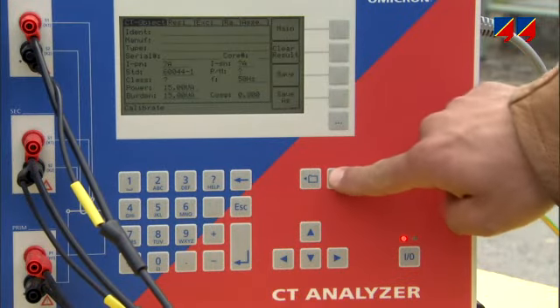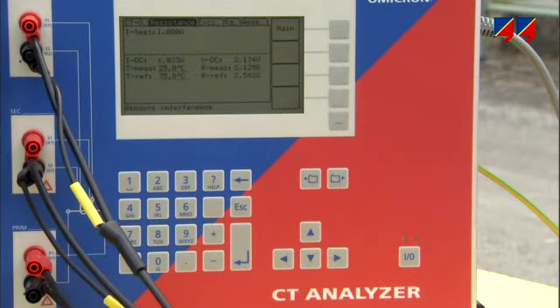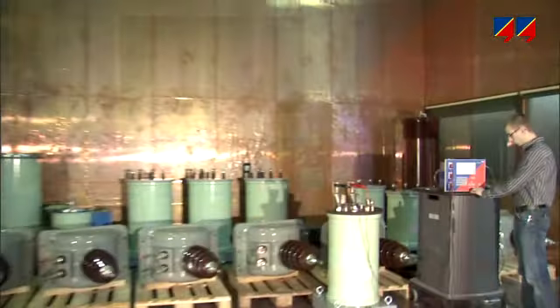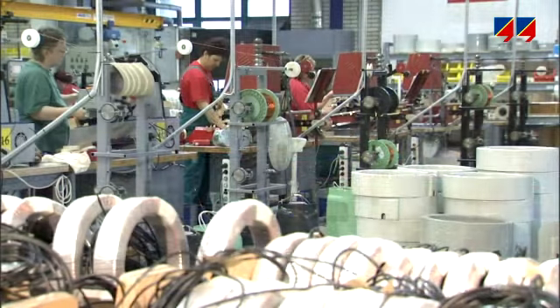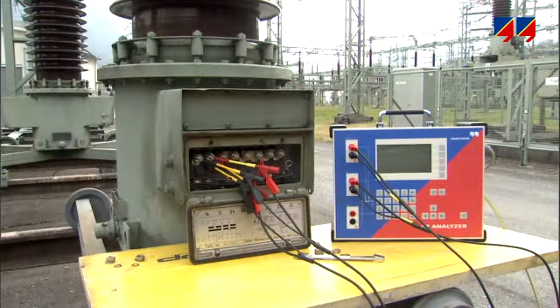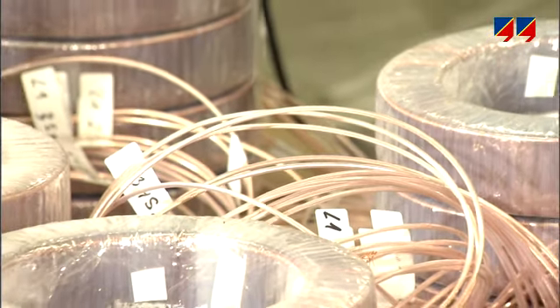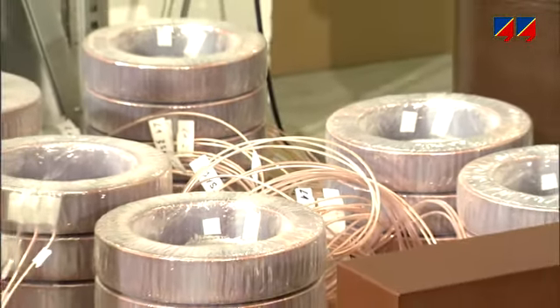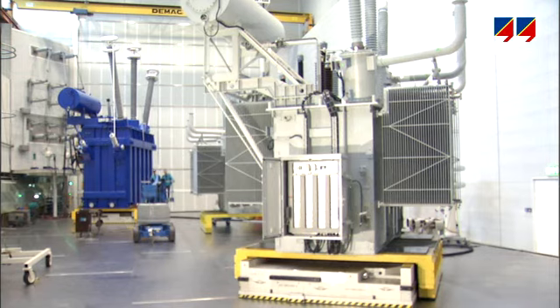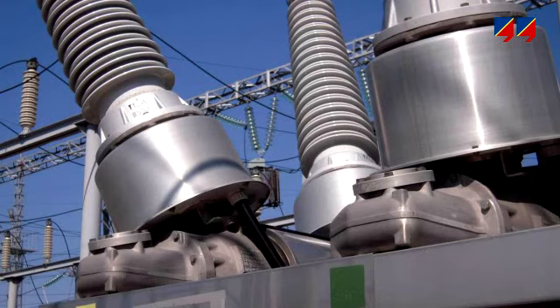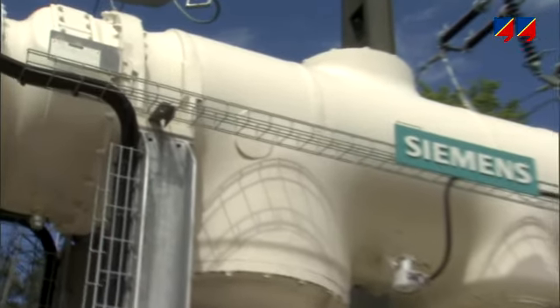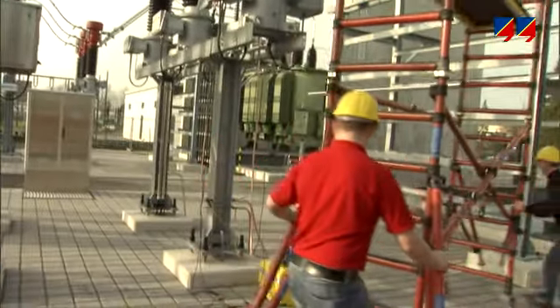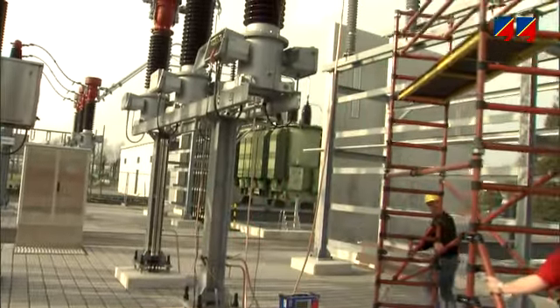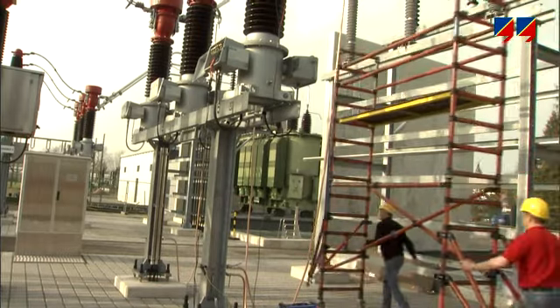Omicron CT Analyzer uses the latest technology, allowing a complete and precise measurement of all relevant CT parameters for use in laboratories and test fields, as well as on-site field conditions. It is suitable for testing all CTs, low, medium, and high voltage types, CTs installed in transformer bushings, circuit breakers, or GIS, for factory, commissioning and recommissioning tests, or for any periodic inspection during the CT's lifetime.